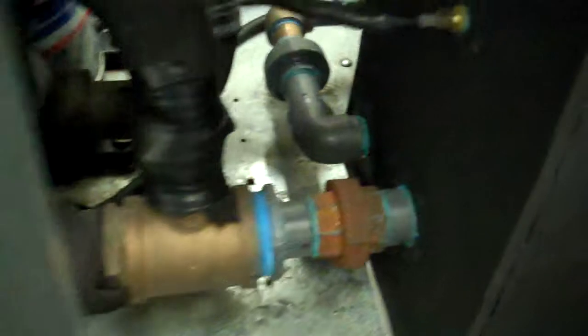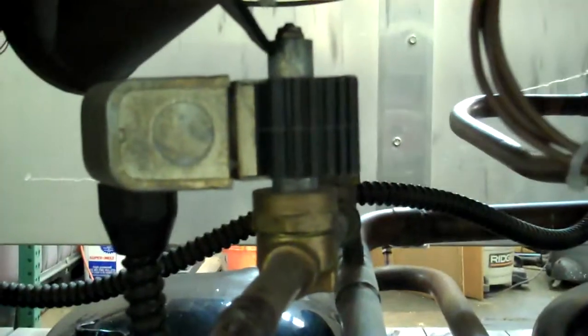This here is our 7.5 horsepower process pump. So this is a process pump and a recirculation pump. We take our suction out of the tank, and then that goes right back out to the process. And at the same time, we're receiving some of the chilled fluid here from the 2 horsepower flow of the recirculation pump. That's coming out of our brazed plate heat exchanger there. That's our flow switch. That's our hot gas bypass valve. Let's walk around the other side of the chiller here.